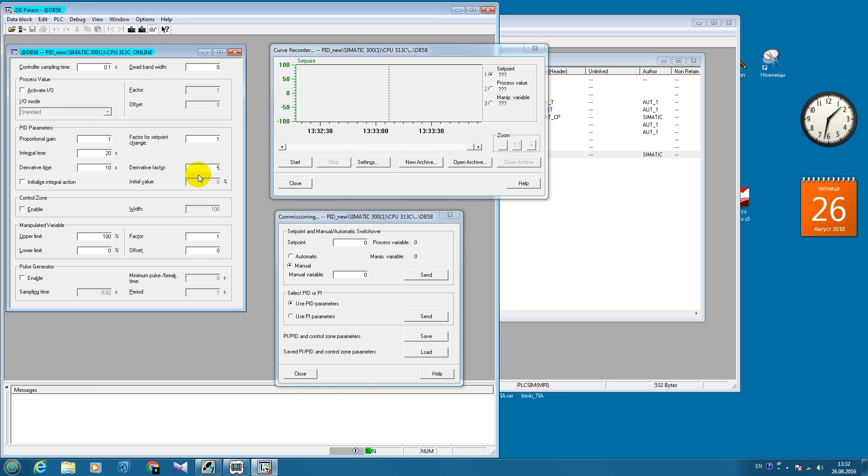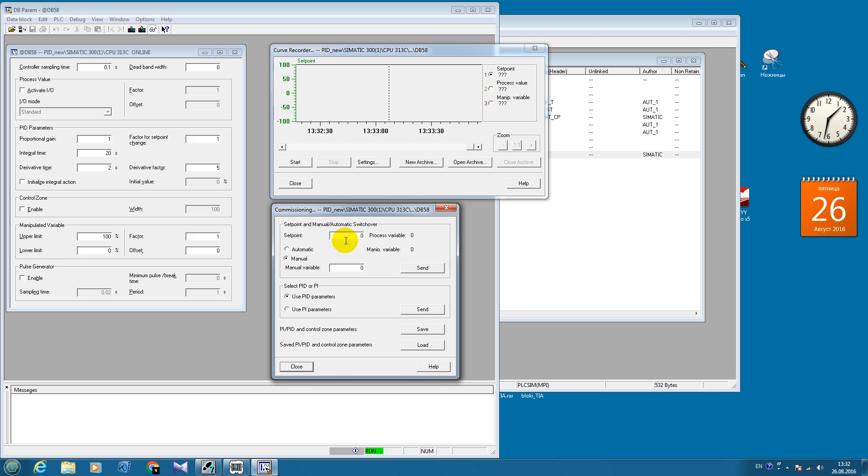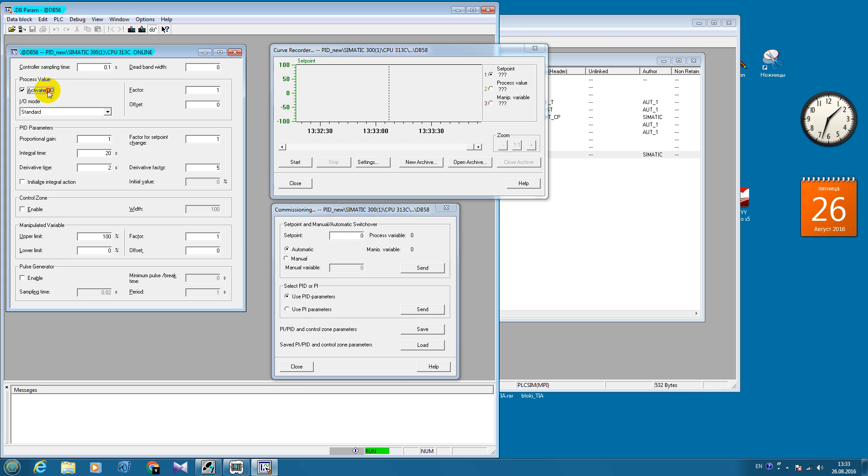In these boxes you can add your PID controller parameters. In the commissioning menu, you can switch over between manual and automatic modes and also you can put your set point value. After you have changed the PID controller parameters, we need to download the block data. The configuration data was loaded.